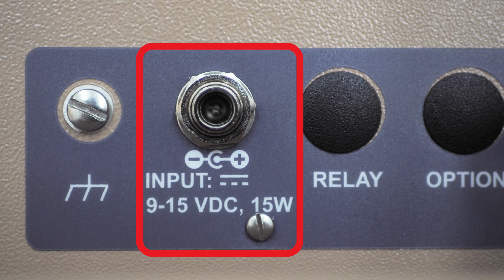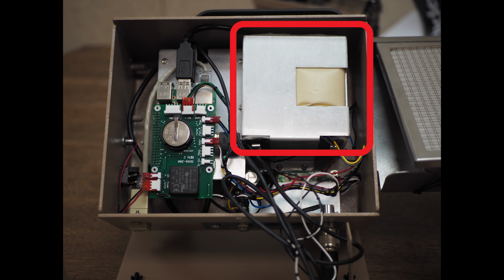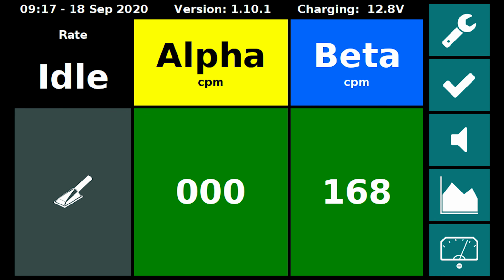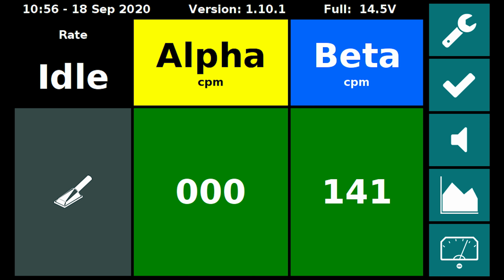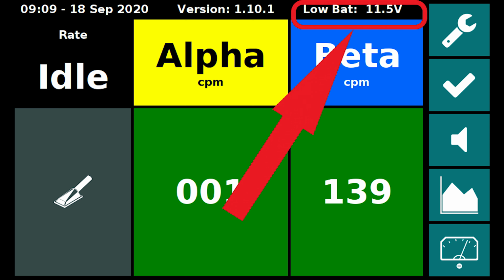This unit is operated from a 120 volt outlet with the use of a 12 volt DC transformer and can operate from 32 to 104 degrees Fahrenheit. A built-in battery provides backup power for approximately 8 hours of operation. The instrument includes a charging circuit to keep the battery refreshed, as well as a low battery indicator on the LCD that will warn you when there's less than 2 hours of battery life remaining.